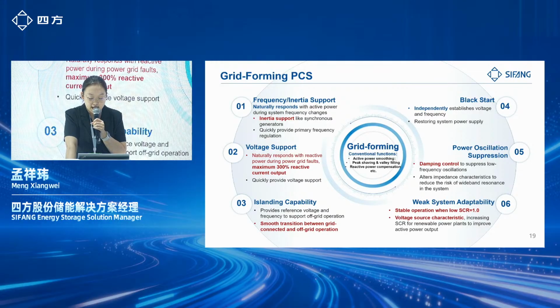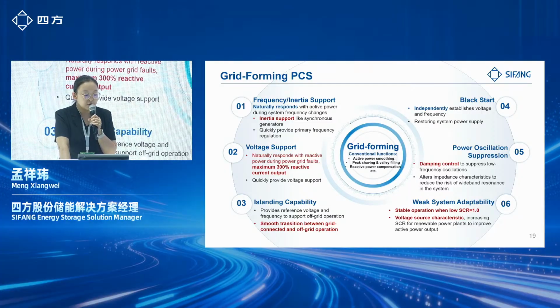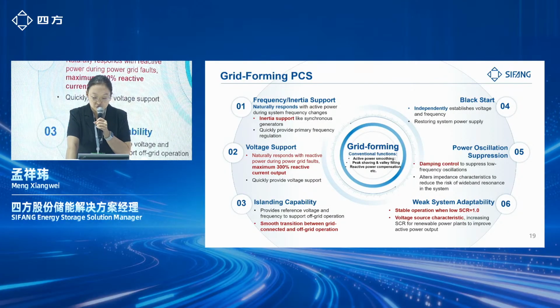Besides the grid-following PCS, we also have the grid-forming PCS. As our colleagues described before, the advantage of the grid-forming PCS is to perform frequency and inertial support during frequency change of the power grid, and the response time of the inertial support is very fast. Also, during a voltage fault of the power grid, it can provide active voltage support and maximum 300% reactive current output.